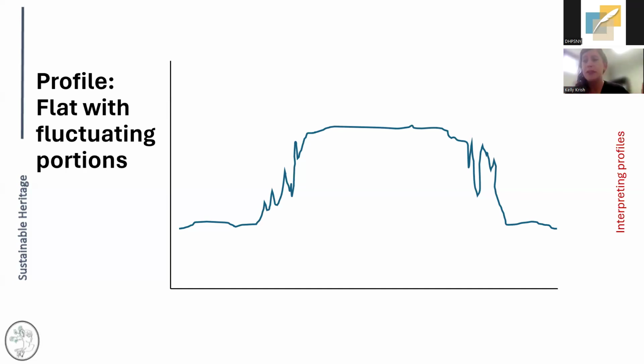But a lot of times people will see this in their data and think that there's something wrong with the mechanical system that needs to be addressed. Replacing the mechanical system in this instance won't change what the graph looks like. If it is an issue with the relative humidity for collection, it'd be something you'd want to look at the programming for, or even something larger. I've seen it a lot of times with libraries on college campuses. The chilled water comes on at certain times of the year. So if you hit a humid point before that is activated campus wide and you can't dehumidify, your relative humidity will go up. Changing out that system won't do anything because you don't have the chilled water coming from the supply to do anything with it.